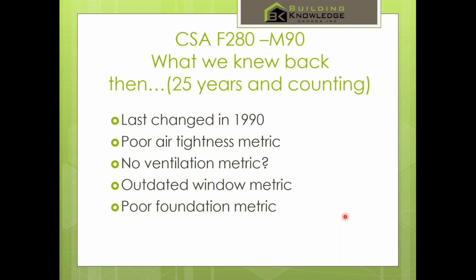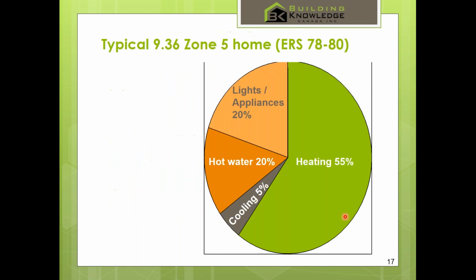The old one, the M90, 25 years ago, in reality, had little changed in, I'm going to say, 20 or more years. It had a very poor air tightness metric. When I say poor air tightness, it was based on an air tightness algorithm out of California that the US still uses, and no ventilation metric whatsoever. So the old M90 actually did not account for ventilation air. That was only added later by associations like HRAI or TECA that said, hey, you might want to add ventilation into your load calcs. It also had a very poor window metric and a poor foundation metric, mostly because we were just starting to understand in the 90s how heat was lost out of foundations.